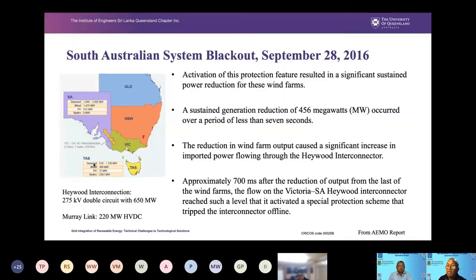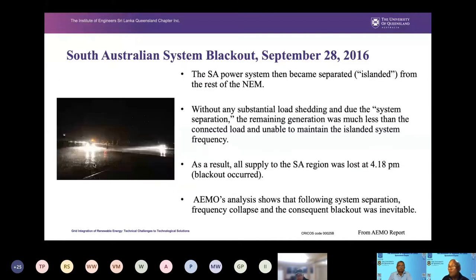Approximately 700 milliseconds after the reduction from the last wind turbine, the Victoria, South Australia, Heywood interconnection reached the maximum level, and then it couldn't tolerate it and tripped offline. Now we have a scenario where an island is formed, even though the Murray Link is still hanging on, but we didn't have sufficient generation in the South Australian system to feed the load. Ideally, the system load shedding should have worked. Unfortunately, the load shedding also didn't work.